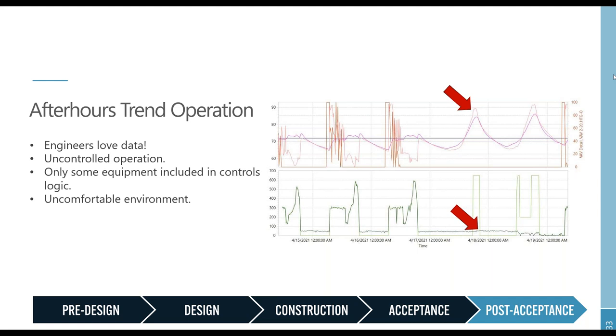We love data. We're very few people who probably get excited when we look at squiggly lines like what we see on the right here. But we get excited because it allows us to find answers, or it allows us to find problems that we can solve. And really, that's what engineers love to do, is to solve problems. So in this case, what we had on the right-hand side of this screen, it's not something major to see, but what we can see here is that on the weekends, during unoccupied operation, these spaces were getting very hot, to the point that some rooms were hitting almost 90 degrees on the weekends when the systems were off. Now, this might not seem like a big issue, but even during unoccupied hours, we want to ensure that our spaces stay at least relatively comfortable.